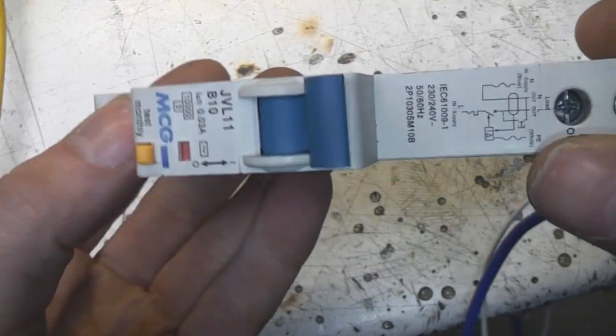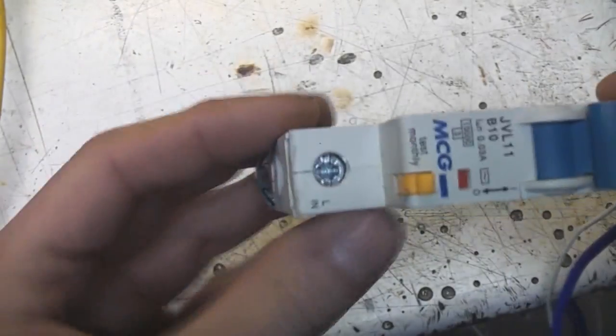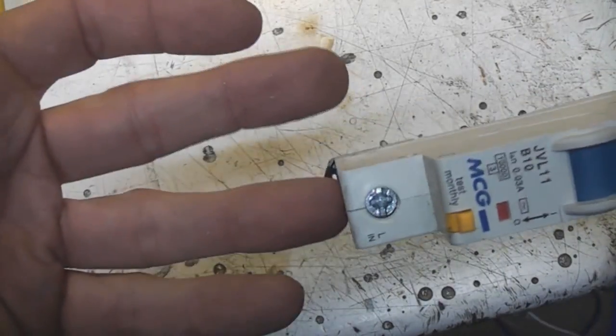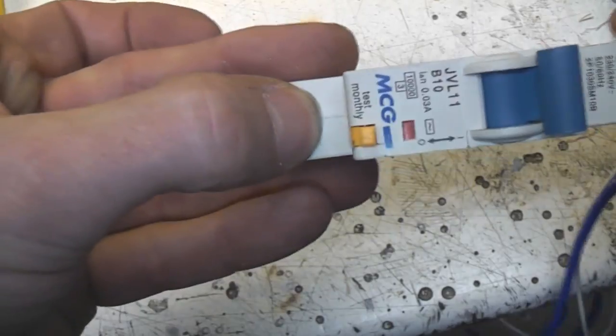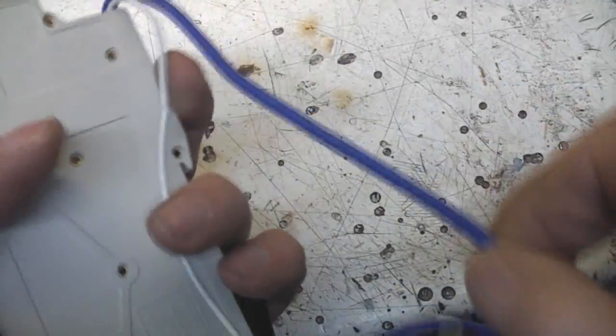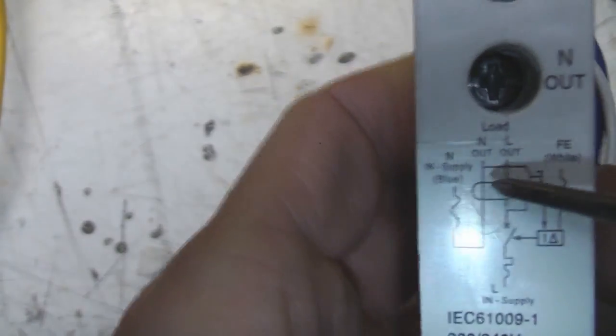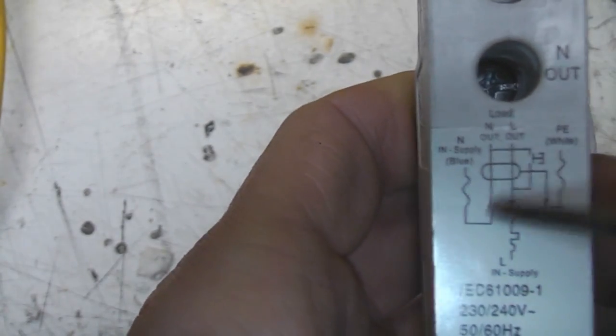Now these are typically installed in a distribution board, and quite often there's a bus bar that's just got tabs on it, so this actually screws directly onto the feed bus bar. There's a neutral wire, because of the residual current capability, it needs to have the neutral, so it has the live and the neutral for this current transformer, but this is only used for the residual current device. This one's also got a functional earth connection.